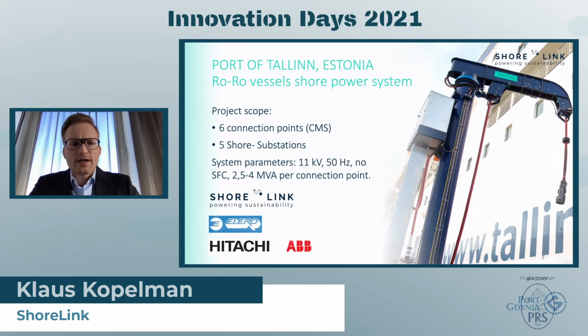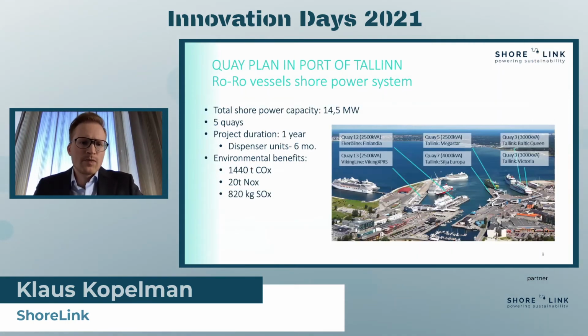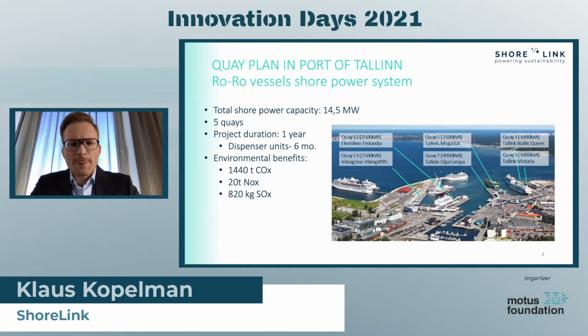Last year we did a project in the port of Tallinn where we installed 6 cable management systems, basically 6 connection points for ro-ro and ro-pax ferries. Direct grid connection was used, and the system parameters can be described as an 11 kV system, 50 Hertz, with no static frequency conversion used. Per each connection point, the power that can be transferred is 2.5 to 4 MVA. The total shore power capacity installed during the project was 14.5 megawatts, and the project duration was fairly short, about 1 year.